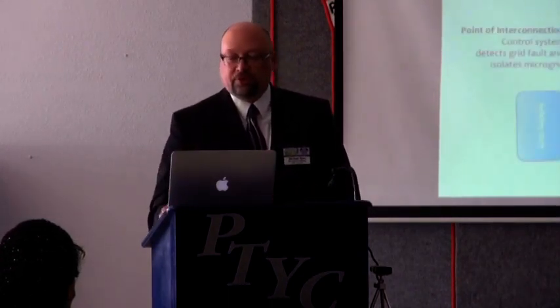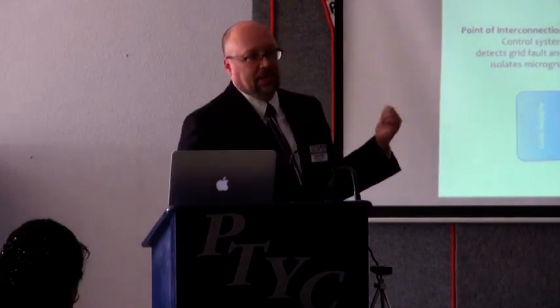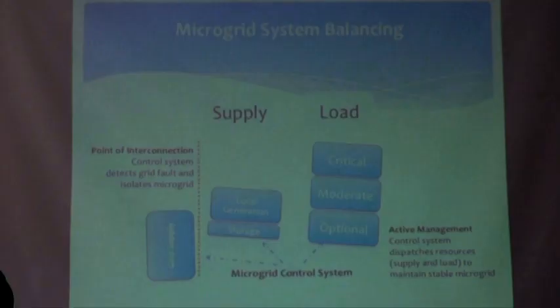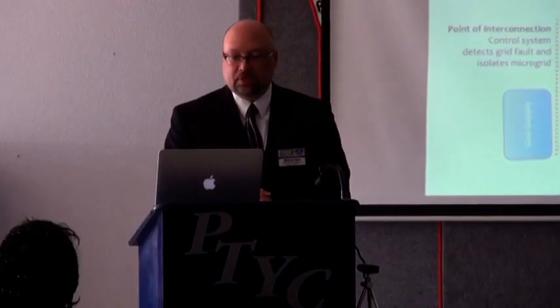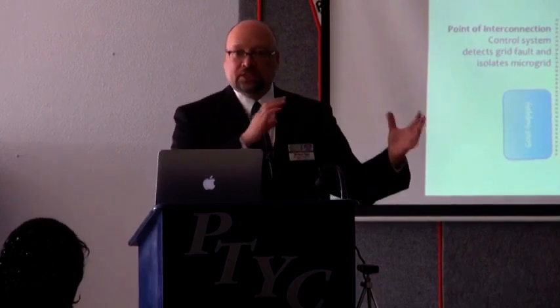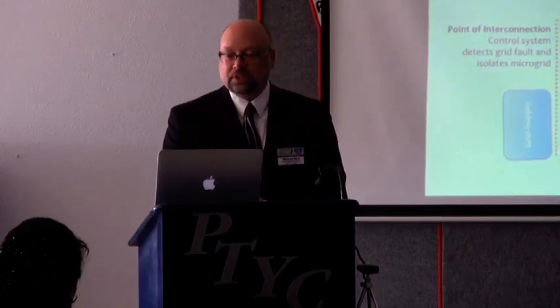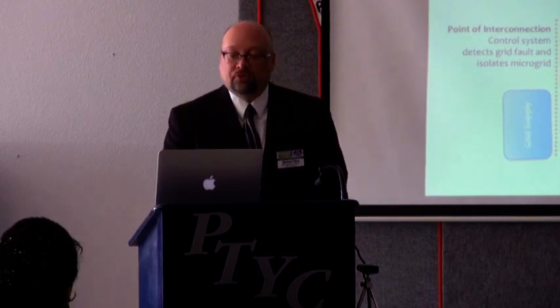The way it reacts: first, you see that orange line separates, isolating itself from the utility grid so it's not accidentally feeding power onto power lines that line workers anticipate to be dead. If you're out there trying to fix the line, you think the lines are dead, and somebody has a generator feeding power onto it, you're going to get electrocuted. So a microgrid automatically isolates to avoid that problem—it's a safety issue, and it also protects equipment on the utility's distribution system. That's the first thing it does.